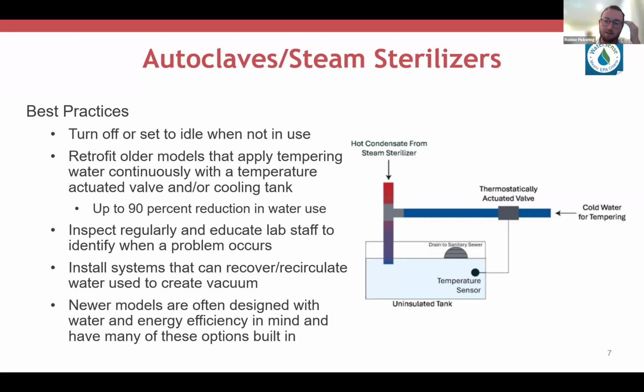I just mentioned inspecting needle valves, but the same exact thing applies to solenoid valves as well. When you've installed one of these retrofit systems or a solenoid valve to help control your tempering water use, these valves often fail, and when they fail open, that will just return your system to running water continuously. Posting signage or educating staff is really a great way to help identify when these failures occur. And Star Scott from University of Georgia is going to talk about her program and associated user education a little bit later.